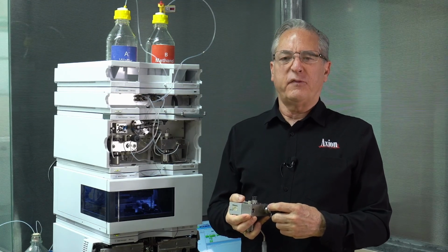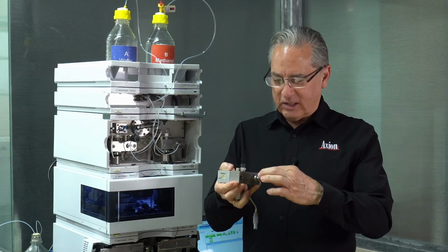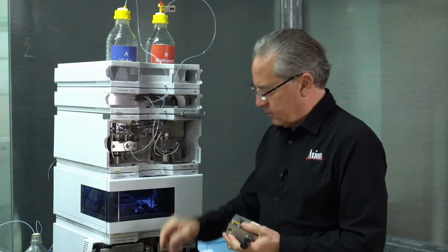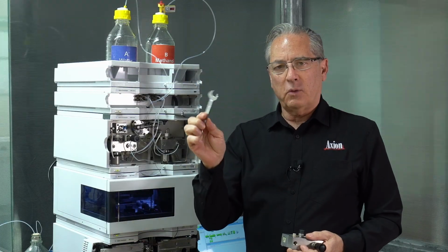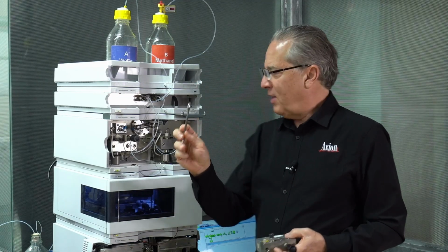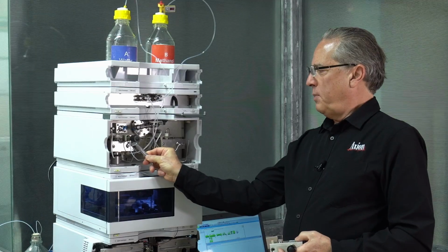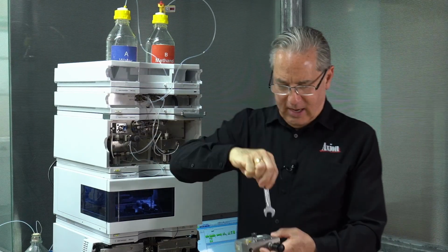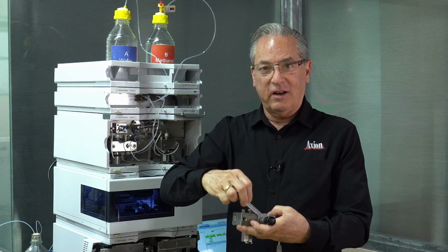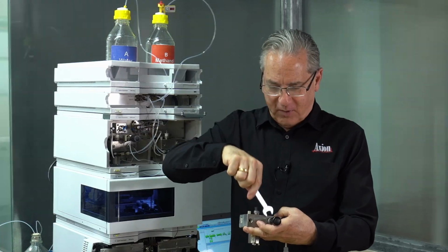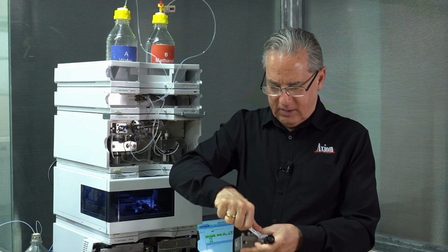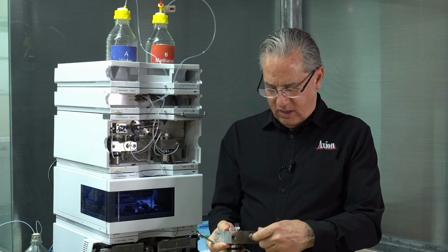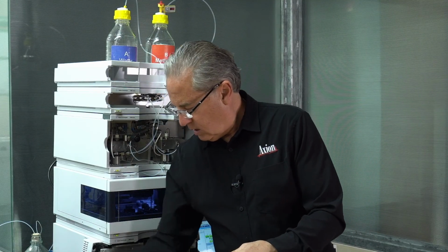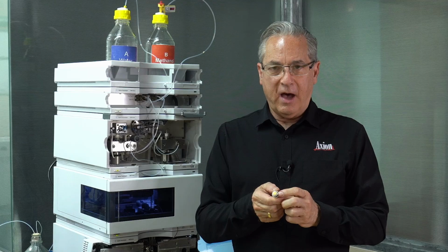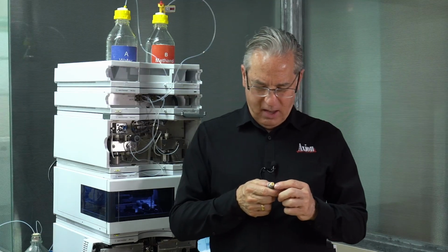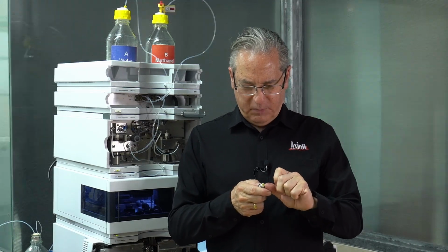It's called the PTFE frit. I call it a cigarette filter. It looks like a cigarette filter. And if you remove this purge valve, there's a little wrench that comes with your LC. It's a 14 millimeter flat wrench. It fits right behind, right in that little slot. It fits right here. It's hard to find a skinny one, can't find that at the Home Depot. So you go in here and you loosen this guy up. And when you take it out, on the inside, you have what's called a gold seal. And this you just pop off with your thumb.